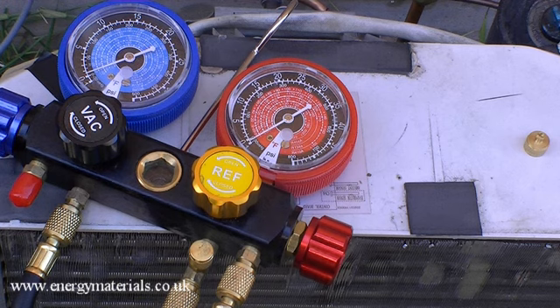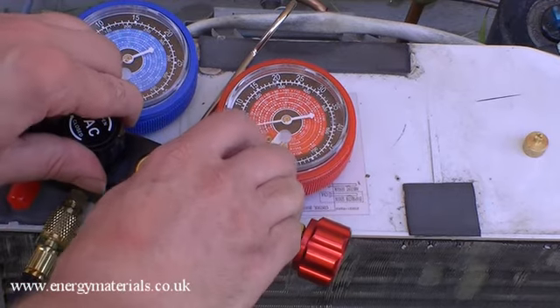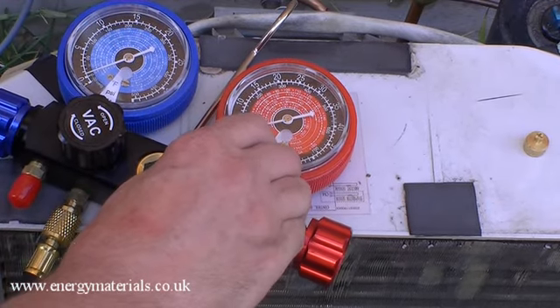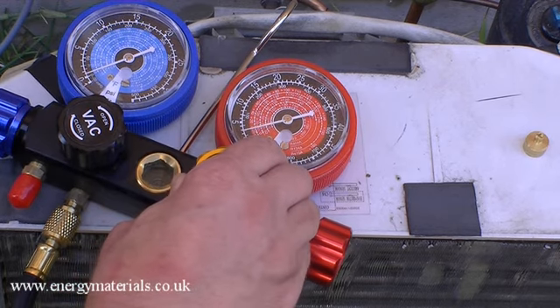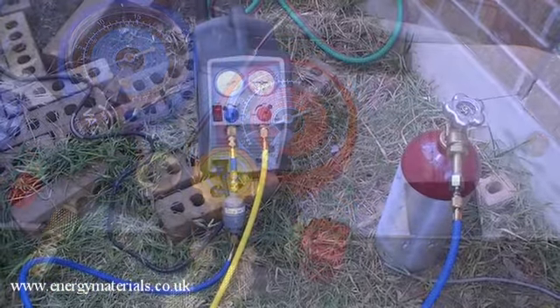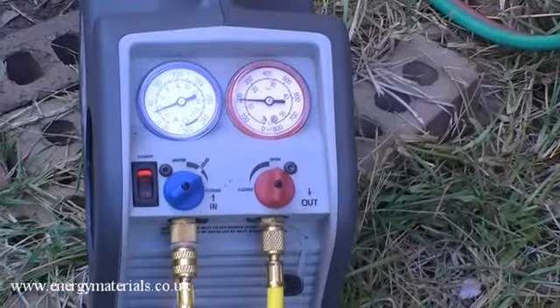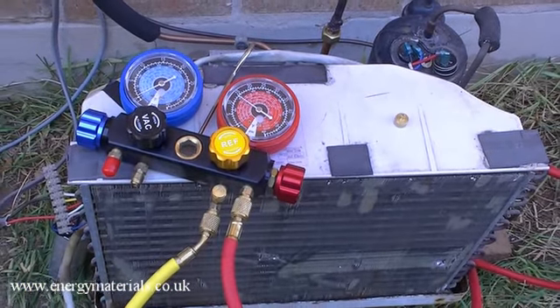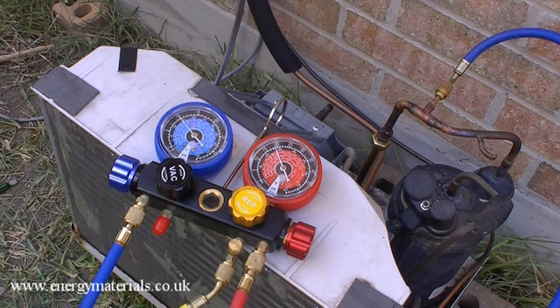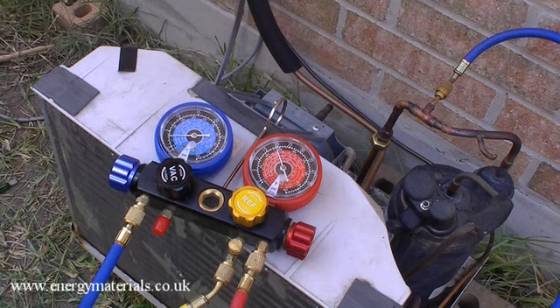Okay, so we evacuated it. So the high pressure side is connected, so I'm going to turn the vacuum system off and I'm going to allow refrigerant into the high pressure side. Now we use the refrigerant recovery machine to transfer all the recovered refrigerant back into the new system. So the refrigerant is back in the system, I think we're now good to switch it on. Turn on both fans and the compressor. Okay, so compressor's running now.